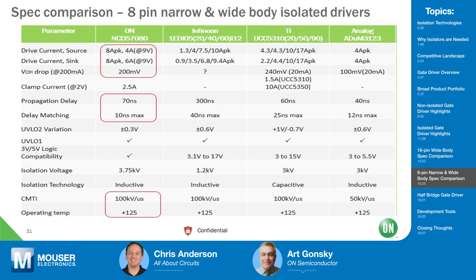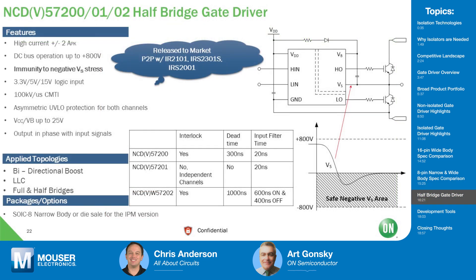Comparing the ON Semi NCD57080 versus Infineon, TI, and Analog Devices: ON Semi delivers 8 amps peak — with 8 amps source and 6 amps sink at 9 volts continuous drive. Output drop is only 200 millivolts, propagation delay is 70 nanoseconds with delay matching of 10 nanoseconds — critical when driving multiple parts on the high side simultaneously, as mismatched timing causes one part to sink all the current and potentially fail. Under-voltage lockout variation is held to 300 millivolts, well below competitors, with 100 kilovolts per microsecond CMTI and a 125°C operating temperature for industrial applications.